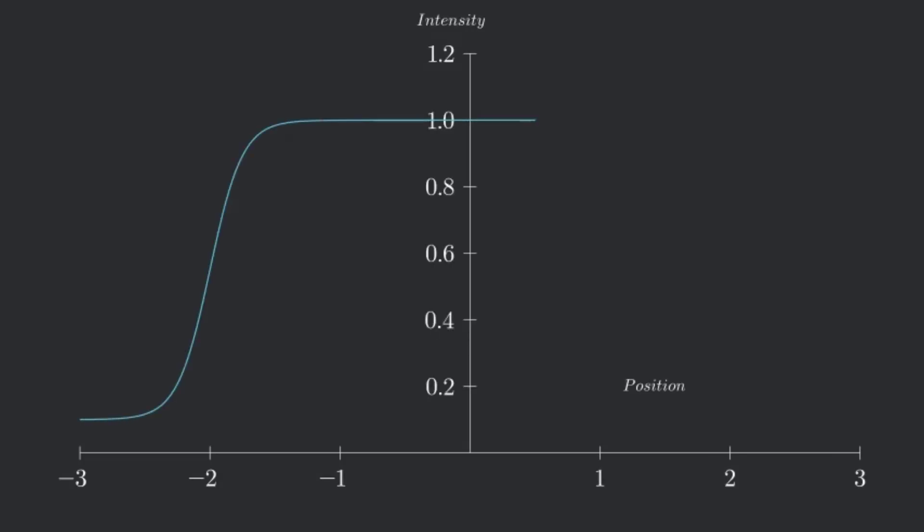Let's take a closer look. Here we have a radiation beam profile, and at the 50% isodose line of the full-width-half-max, and that's where we define our field size. It's not the size of the physical collimation, rather the width measured symmetrically at the 50% isodose line.